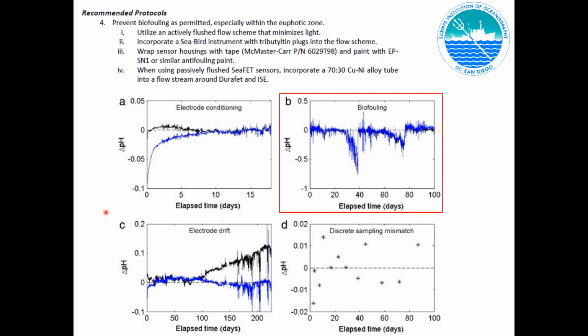And so what we're looking at in this figure is the deviation in the upper right, deviation between two sensors, one of which is not fouling and the other is fouling. And of course, when you get up to an error in pH of 0.5, it should become pretty obvious there, even based on discrete samples. But what we'd like to do is identify the very onset of biofouling at the 0.05 pH level. And in order to do that, it's extremely helpful to have co-located sensors deployed.